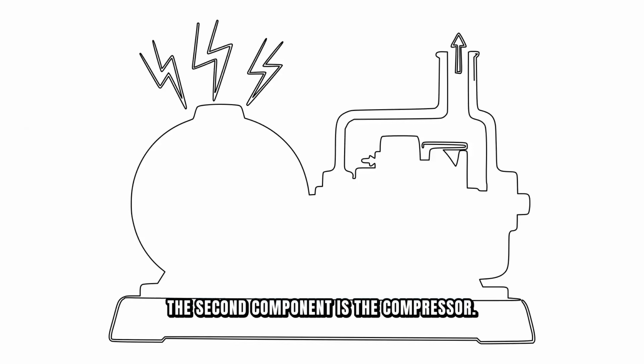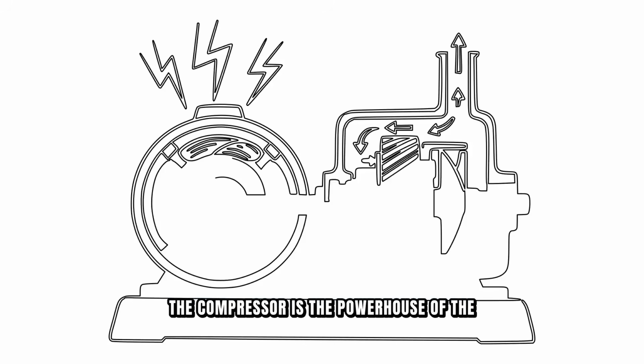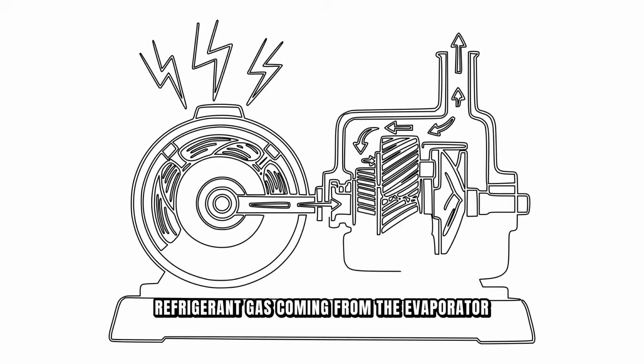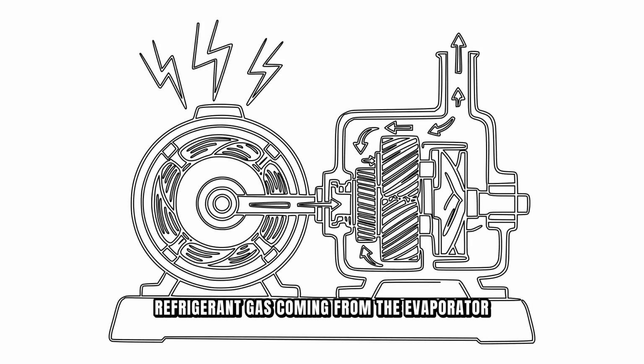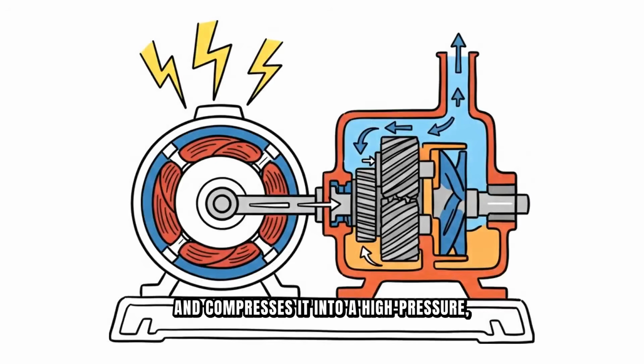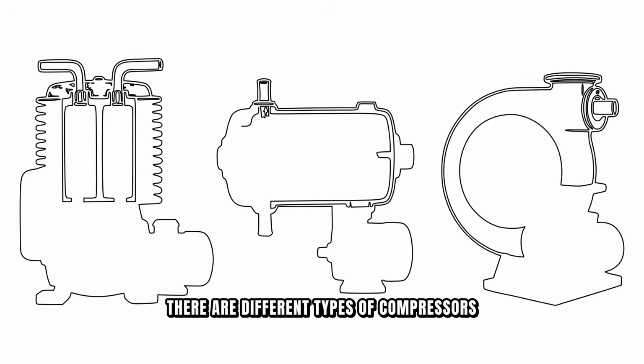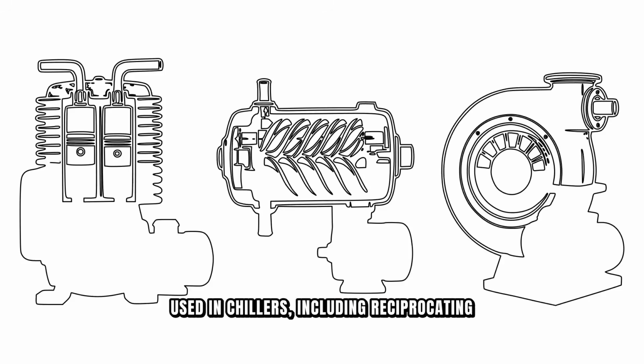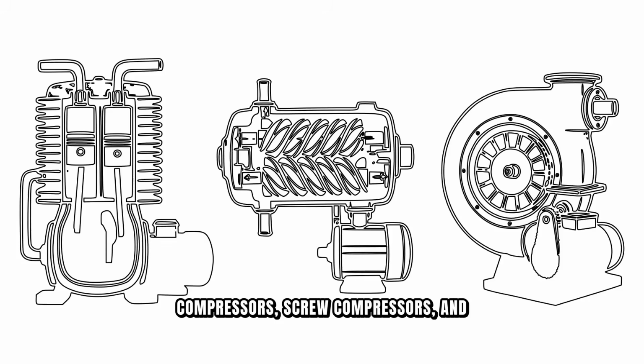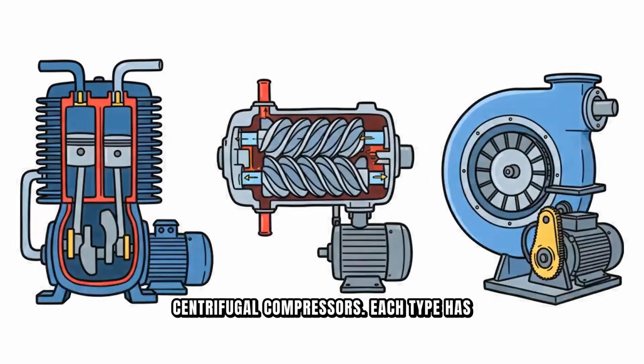The compressor is the powerhouse of the system. It takes the low-pressure refrigerant gas coming from the evaporator and compresses it into a high-pressure, high-temperature gas. This requires significant electrical energy, which is why chillers can be power-hungry. There are different types of compressors used in chillers, including reciprocating compressors, screw compressors, and centrifugal compressors. Each type has different applications depending on the capacity and efficiency requirements of the system.